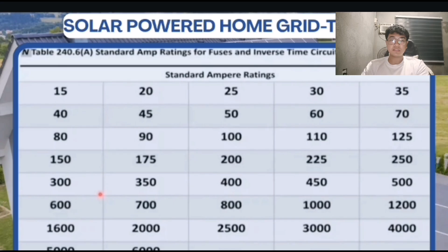It lists the standard ampere rating for fuses and inverse time circuit breakers. When an electrician or engineer calculates the required protection for a circuit, they must usually select a fuse or breaker that matches one of these specific ratings. So, in a grid-tied solar system, you need these ratings to properly size the overcurrent protection for the photovoltaic source and output circuit, the inverter output circuit connecting to your home main panel, and the main service panel itself.